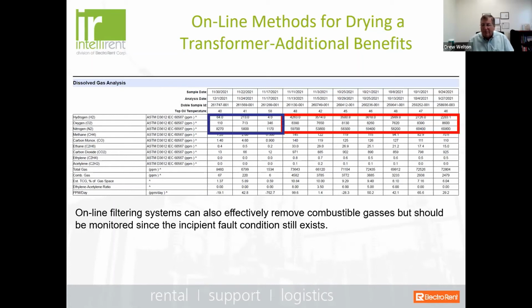Well, the customer was quite upset with the manufacturer and said, look, we want this thing replaced. We've tried to have it repaired at one particular point, and it was not effective. And so the problem, again, we have with lead times was that it was about 6 to 7 months out before then. So they had to keep the transformer online. It was a critical asset. And what they did was they put this filtration system in place. And you can see here these were the extremely high levels of oxygen, nitrogen, and methane. And they put this process in place, and it did a rather good job at keeping the combustible levels of gas in check while the new transformer was being replaced.